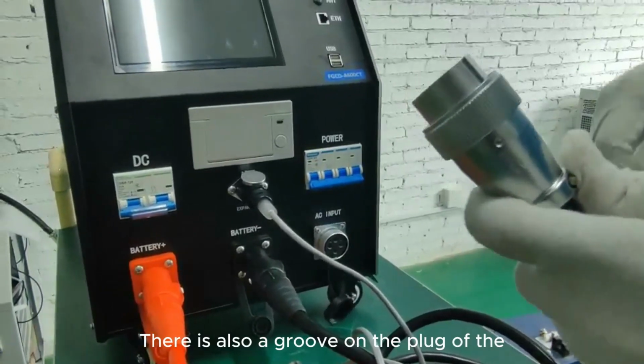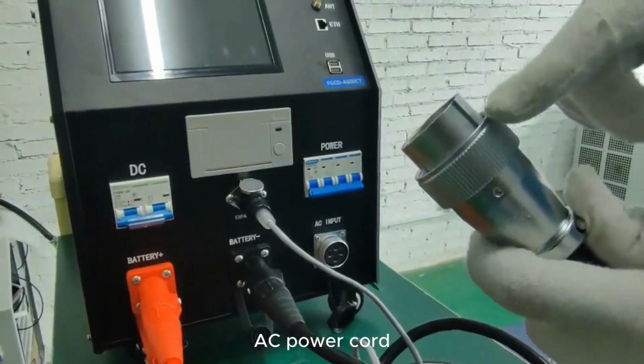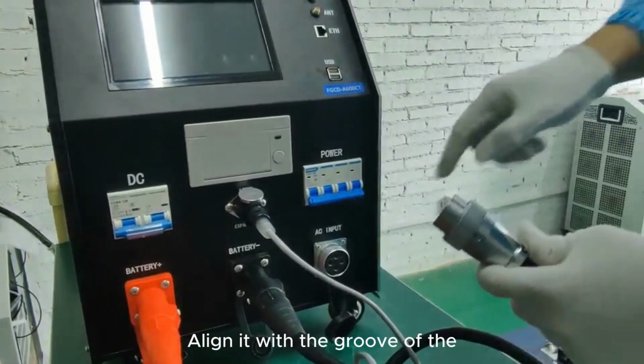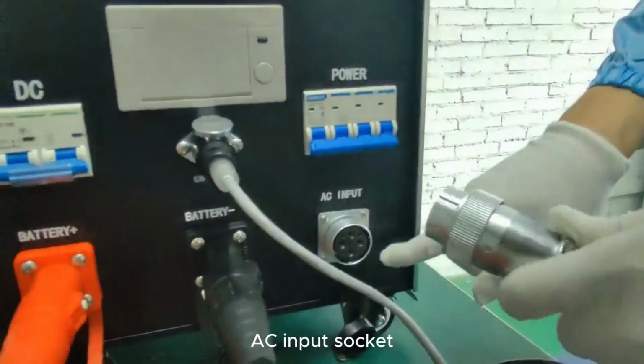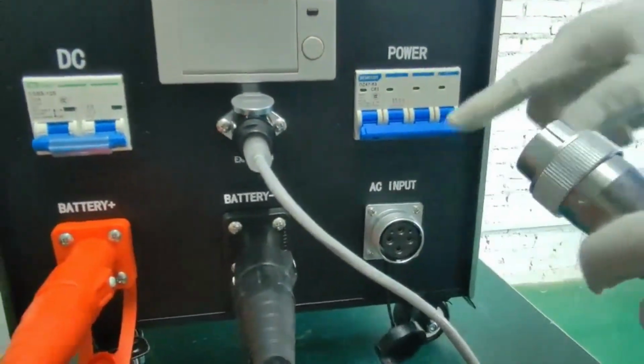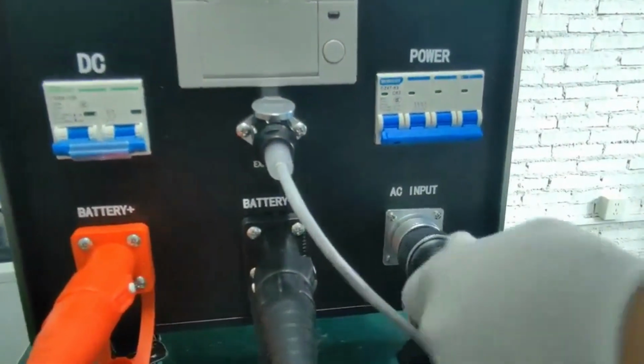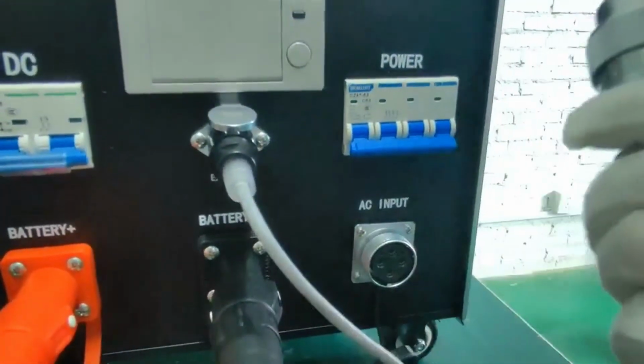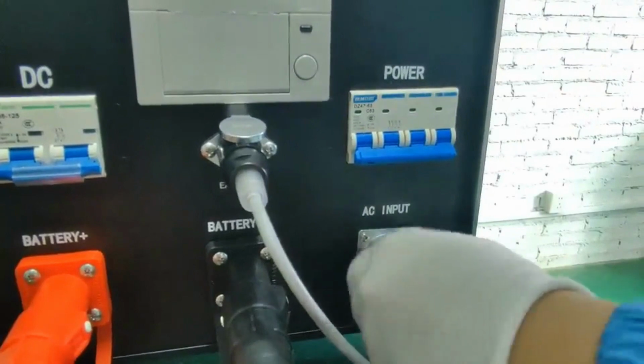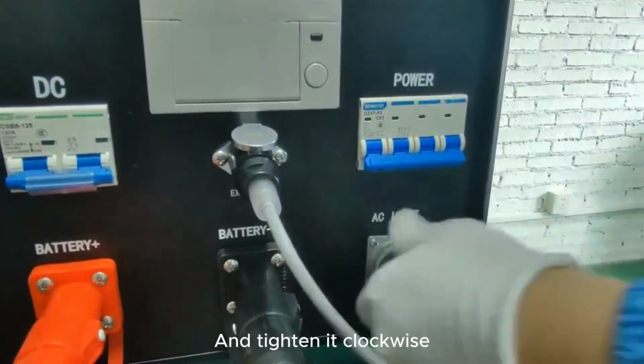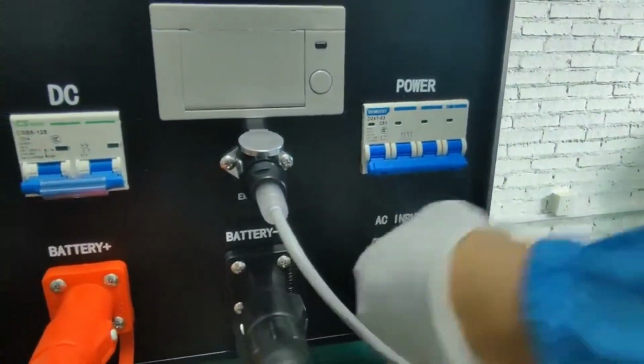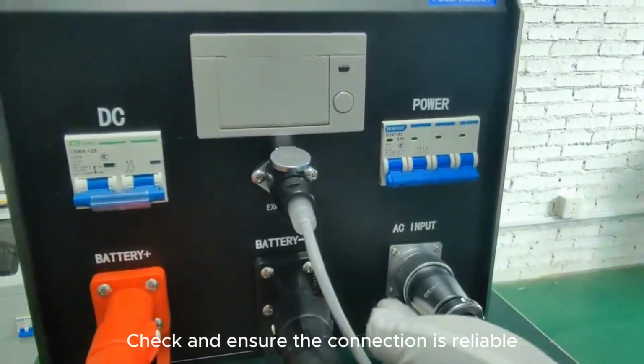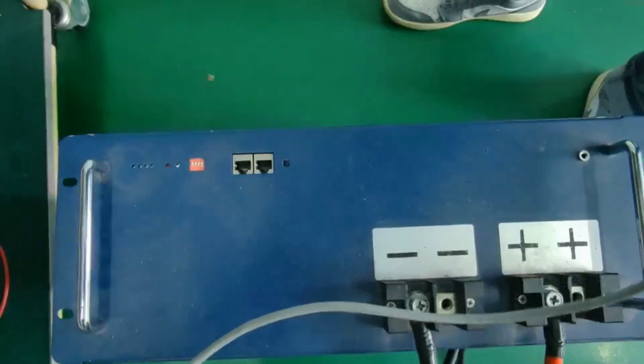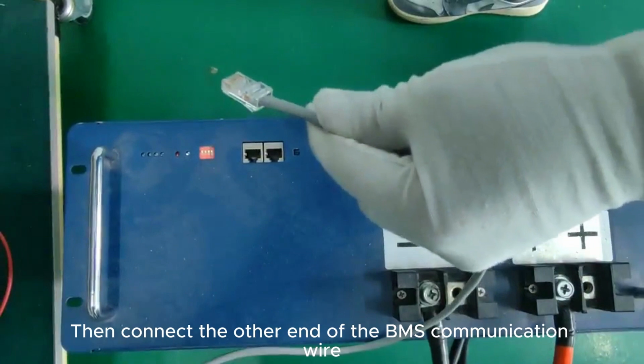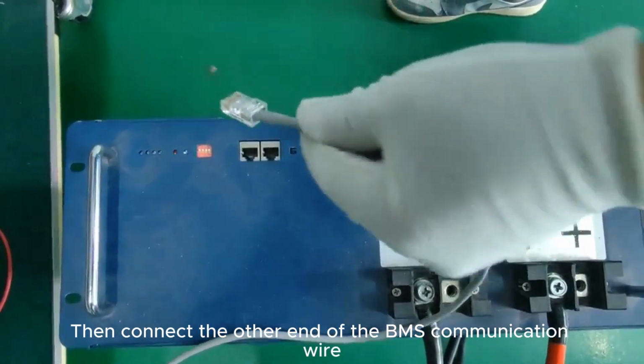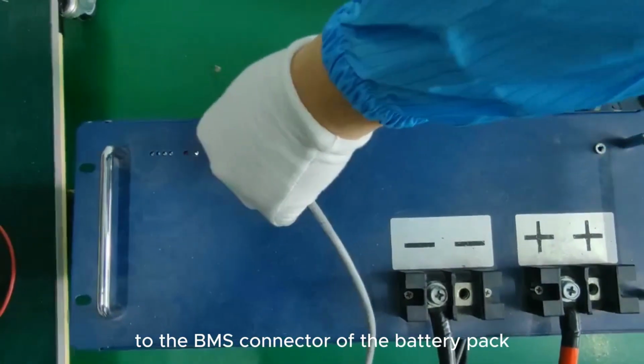There is also a groove on the plug of the AC power cord. Align it with the groove of the AC input socket. And tighten it clockwise. Check and ensure the connection is reliable. Then connect the other end of the BMS communication wire to the BMS connector of the battery pack.